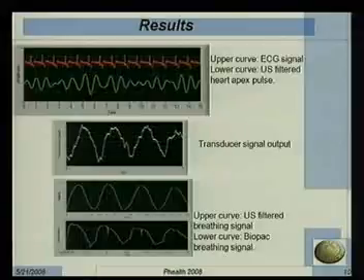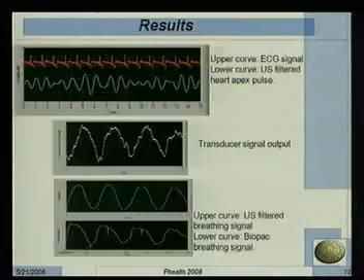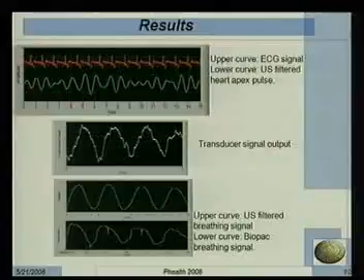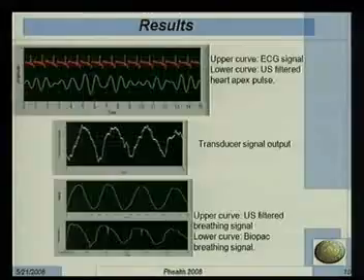Here we have another example of the transducer signal output. The signal was filtered in order to have the breathing signal, and this signal was compared with the output of the commercial device able to monitor and detect the respiration signal, which in this case is the Biopac.